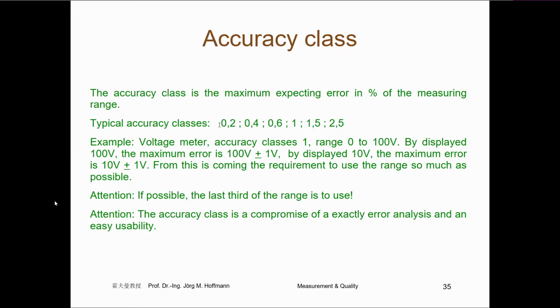Let me give an example. You have a voltage meter with accuracy class 1, and the range is 0 to 100 volts. That means at a displayed 100 volts, the maximum error is 100 volts plus minus 1%, which means plus minus 1 volt.